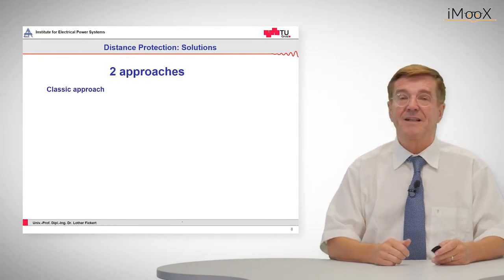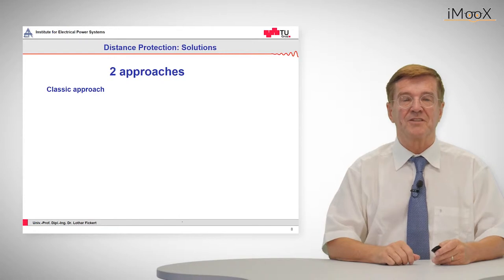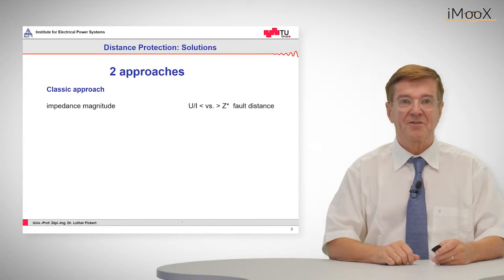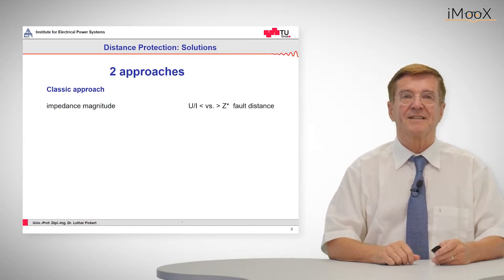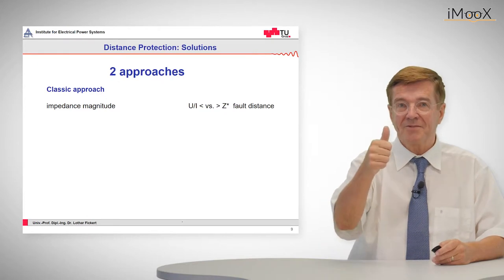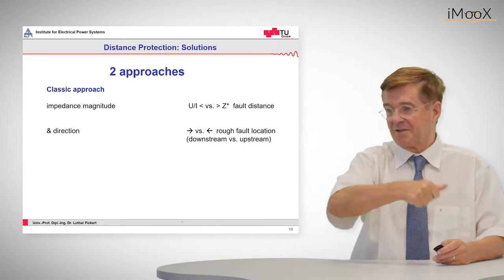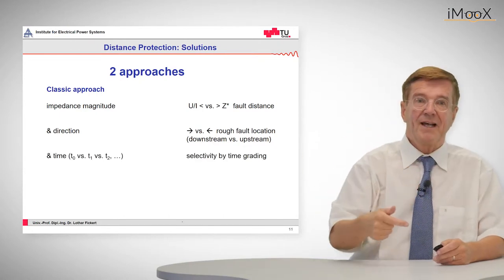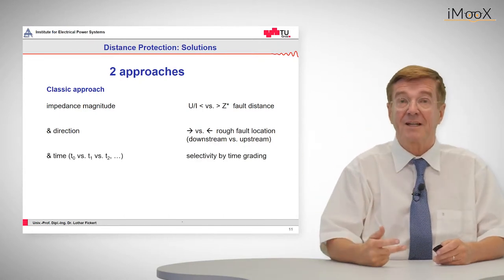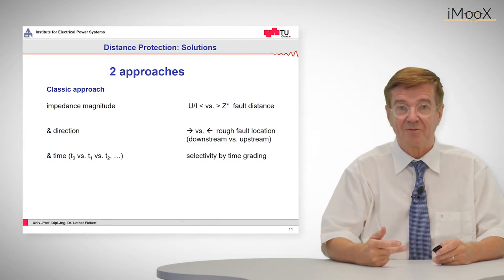So how does the relay discriminate? There are two approaches. One is the classic approach. So the classic approach is that the impedance magnitude is measured, that the direction is determined, is it downstream, is it upstream, and that accordingly a time is respected when to trip.